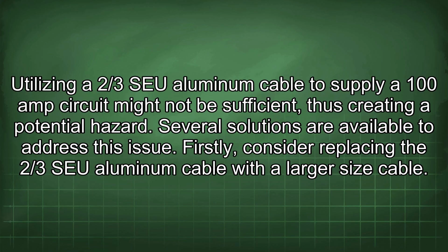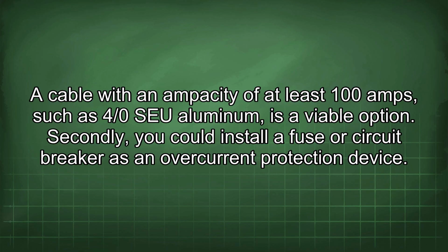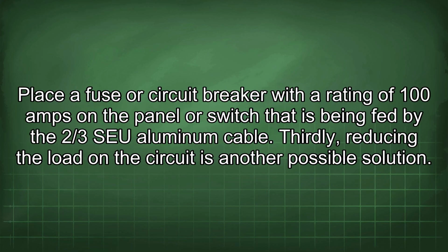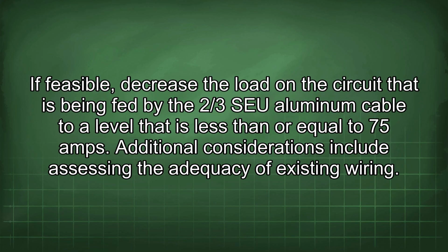Firstly, consider replacing the 2/3 SEU aluminum cable with a larger size cable. A cable with an ampacity of at least 100 amps, such as 4/0 SEU aluminum, is a viable option. Secondly, you could install a fuse or circuit breaker as an overcurrent protection device. Place a fuse or circuit breaker with a rating of 100 amps in the panel or switch that is being fed by the 2/3 SEU aluminum cable. Thirdly, reducing the load on the circuit is another possible solution. If feasible, decrease the load on the circuit that is being fed by the 2/3 SEU aluminum cable to a level that is less than or equal to 75 amps.